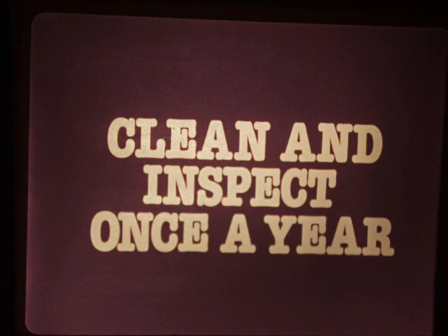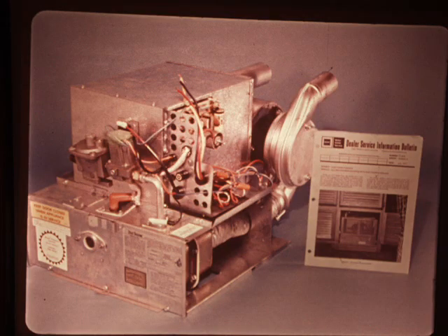Here's one final maintenance tip. It's important that the furnace compartment be kept clean to maintain furnace efficiency. Routine cleaning and inspection is recommended once a year. Review this film and refer to the dealer bulletin on the subject whenever you're called on to service a DUO-THERM furnace.